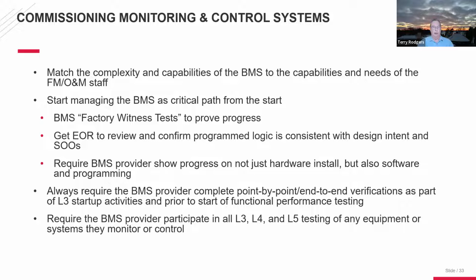If they do it in their office, it's a clean environment. They can build all the panels, do everything, without being out in the middle of a dirty construction site dealing with dust and other issues. They can link the panels and actually build the system in their lab, and instead of 100 feet of cable between panels, it's 1 foot because the panels are sitting side by side on a desk.